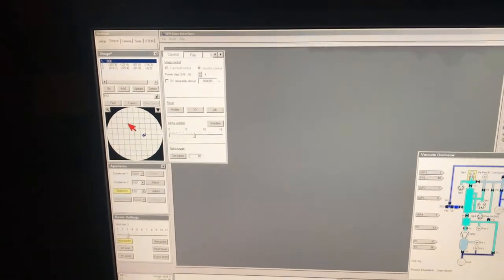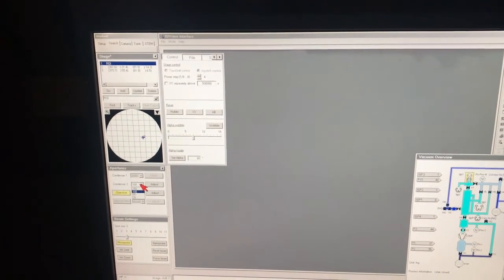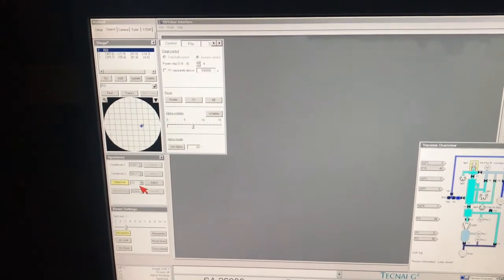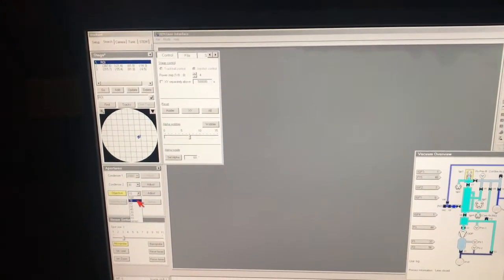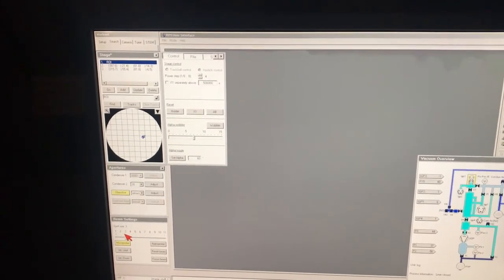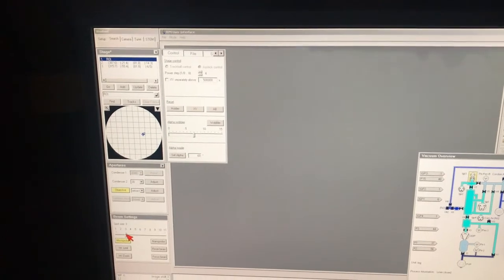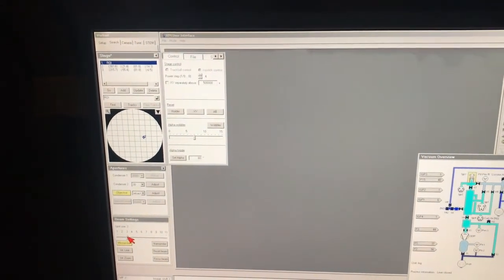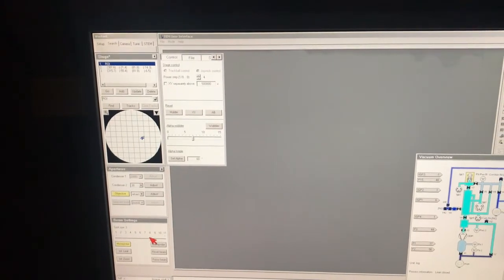When doing the ASTAR acquisition, we use the smallest condenser aperture. In this case, it's 30 micron. Make sure the objective aperture is retracted. To further refine the beam size, we usually use a large spot size number. In this case, we use 9 or 10.